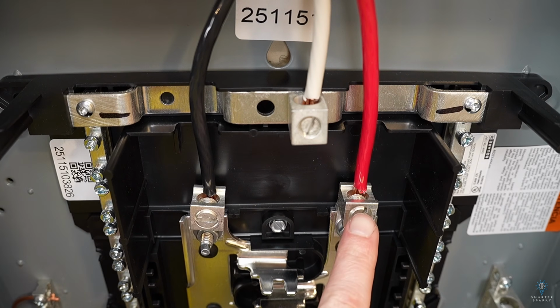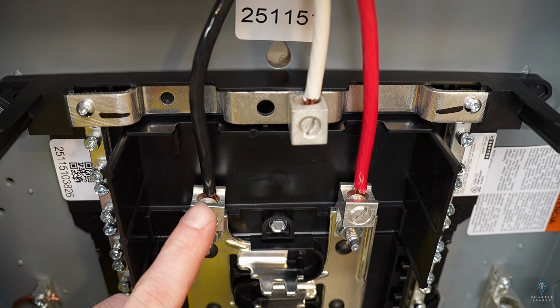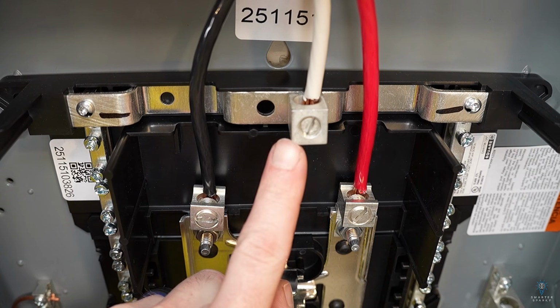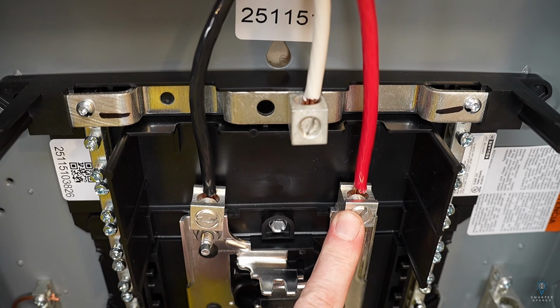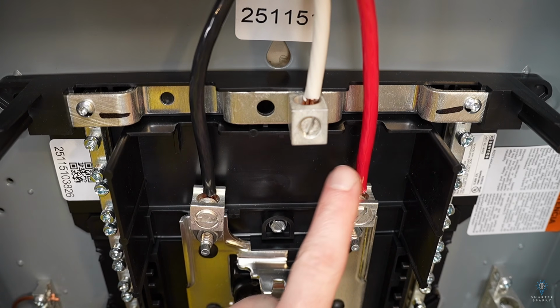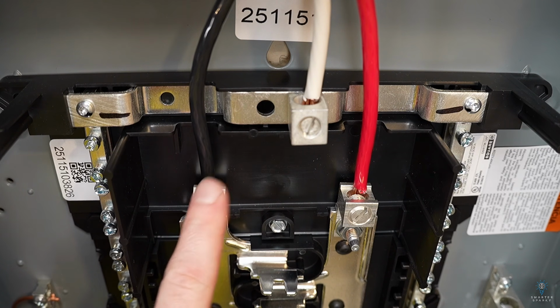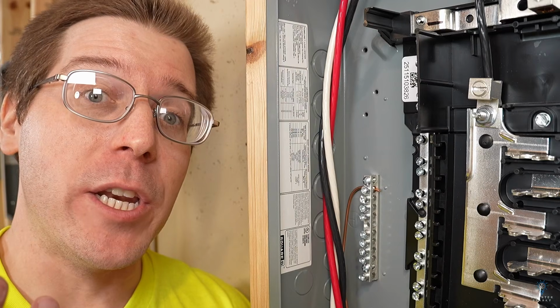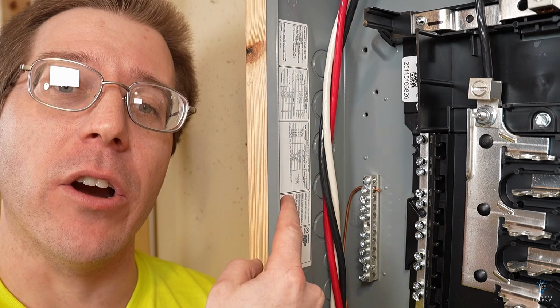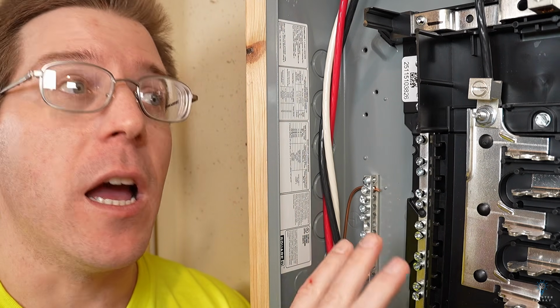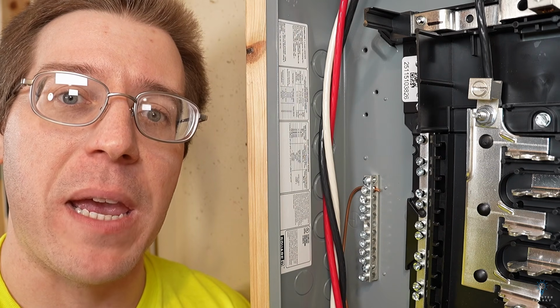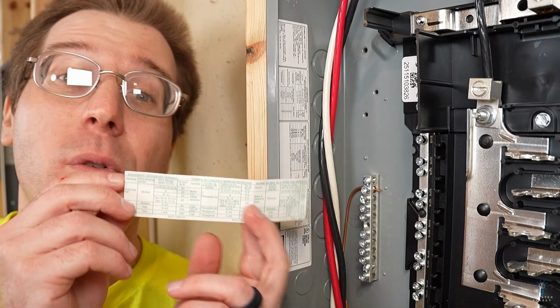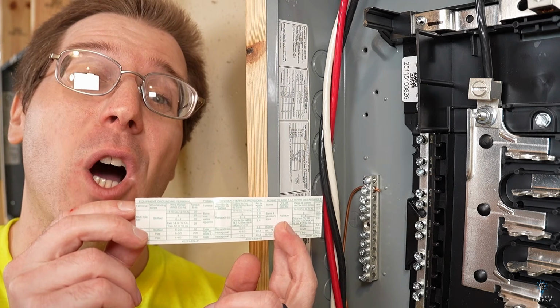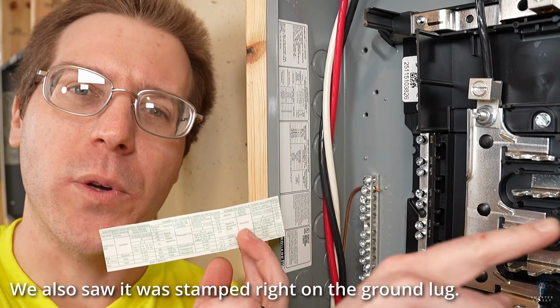If we take a look at these lugs right here, notice how small these wires look inside that opening. These lugs all have a minimum wire size. As a matter of fact, 6 gauge is the minimum wire size for these lugs. How do we know that? Well, this sticker right here actually tells us the lug rating of every lug inside this panel, except for the ground lug. The ground lug kit actually comes with its own sticker that says what the rating of that lug is for.